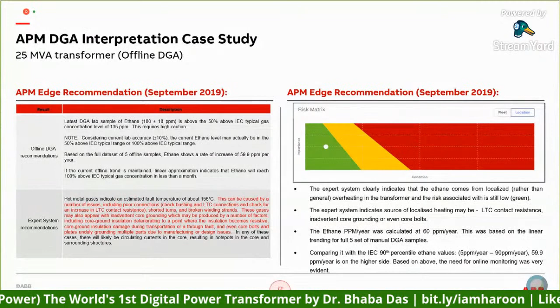So the expert system clearly identified that the gas is coming from localized overheating, and it also calculated the risk associated with that particular cause. And it said the risk is low for that particular DGA result. But the rate of rise was on the higher side, 60 ppm per year, which was based on linear trending of the 5 manual datasets. So based on that, we knew that we needed to monitor.